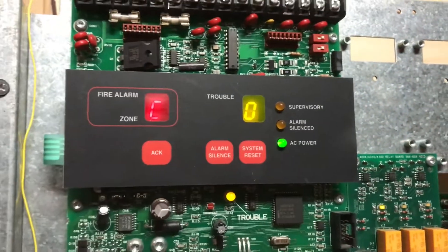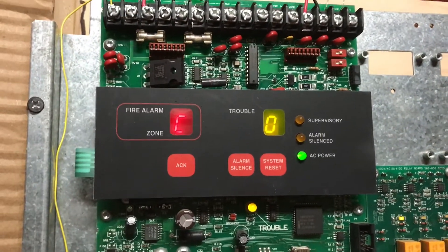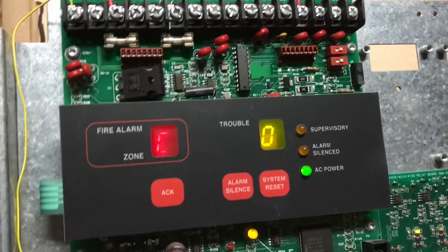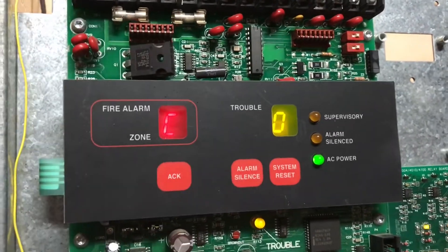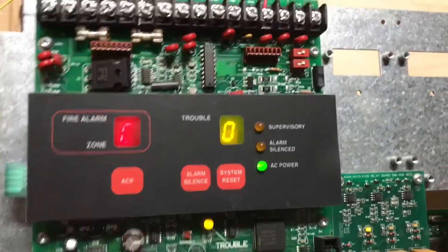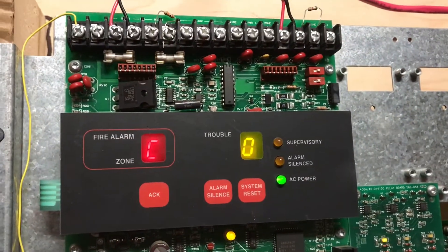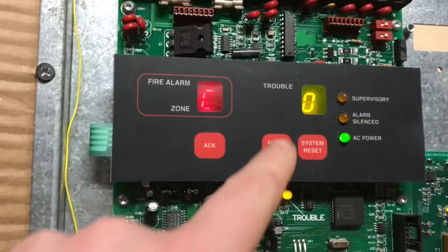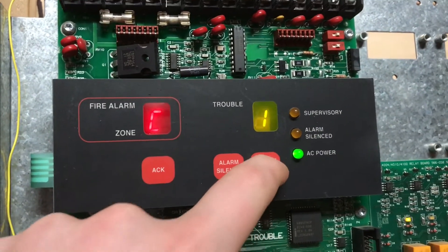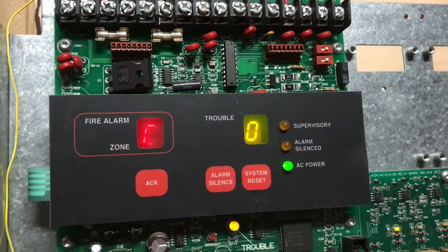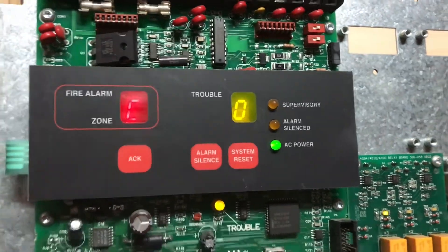C is for alarm silence cutoff. That programs it to automatically silence after a certain amount of time. Your options are 10 minutes, 20 minutes, and 30 minutes. That would be described through one, two, three.